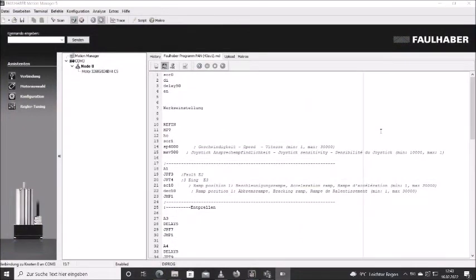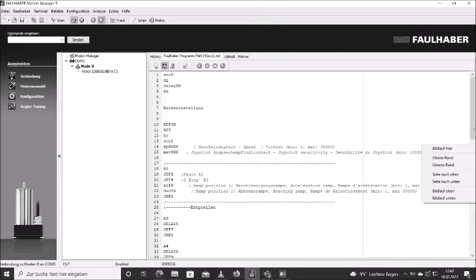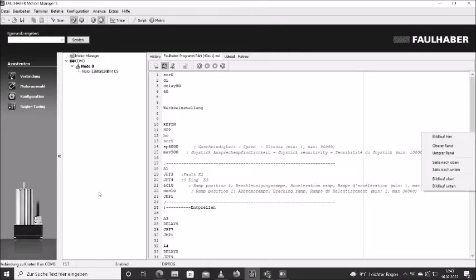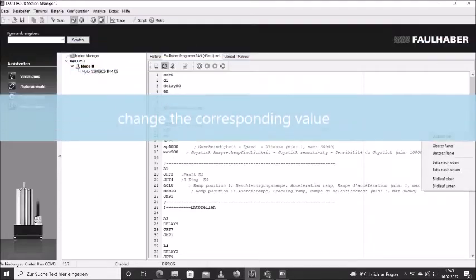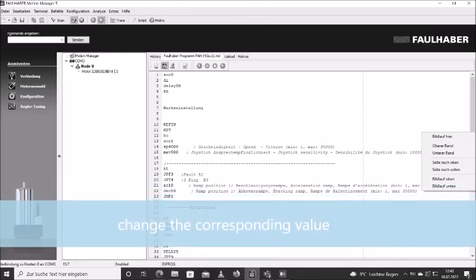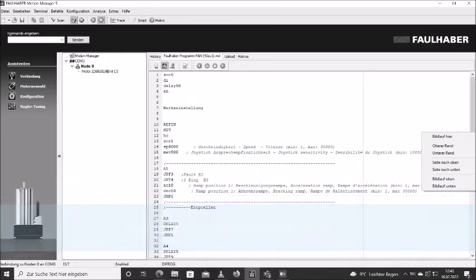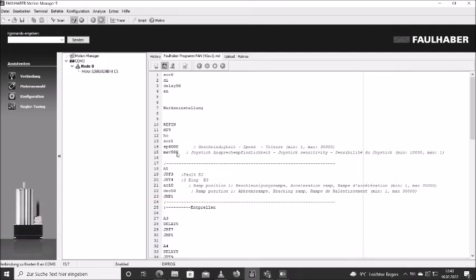To give you an example of how to change the values, I'm going to quickly change the value for joystick sensitivity, which is the MAV value. The joystick sensitivity is now set to 500. You can see here it's possible to set the value between 10,000 and 1, with 1 being the most sensitive value. So if we want to have the joystick more sensitive, we can use value 300.